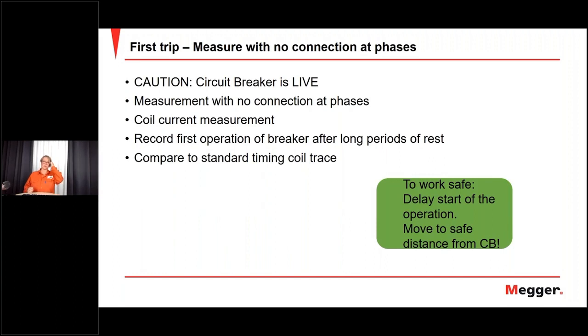And you measure coil current measurement. That's really important during this measurement. And the specific thing here is that you measure the first operation after a long period of rest. If the circuit breaker has been static for a year, as you know, with different greases, there could even be like a bird nest or something in the middle of it.